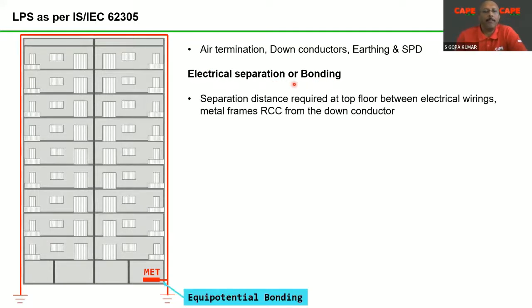What is electrical separation? Electrical separation means the separation distance required at the top floor between electrical wiring, metal frame, and the down conductor. It means the parts of the lightning protection system must be physically and electrically separated from the structural parts of the building. I have better pictures, I will show you. Always the separation distance is calculated with equipotential bonding at the ground floor. Here you see with equipotential bonding, the down conductor and the electrical system are equipotentially bonded.